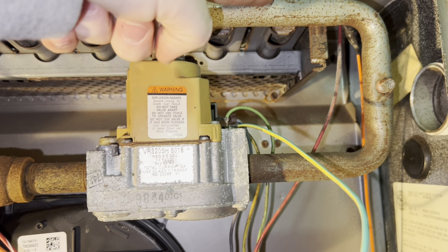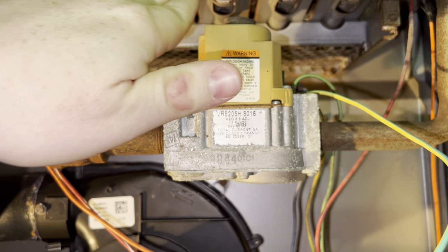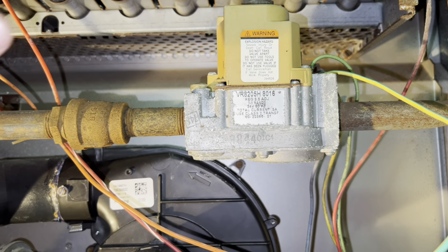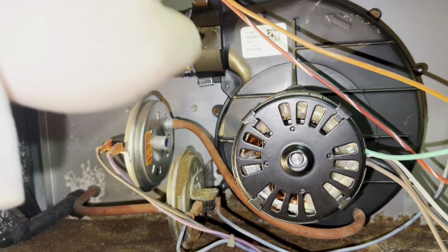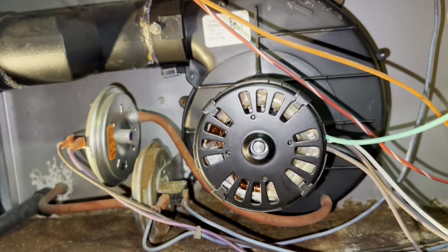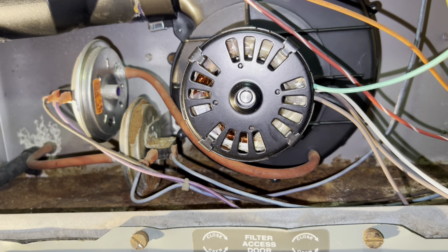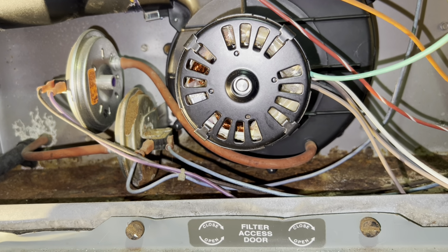And once we are confirmed we don't have any safeties out, the HSI or spark, in this situation it's going to be a spark igniter that's located right up here, is going to start sparking. Our gas valve is going to open. The burners are going to light all the way across. And once they light all the way across, the flame is then going to be proven right here, all the way down. Now we're going to heat up, and then we're going to turn the blower on delay. We want that blower on delay so everything is nice and hot whenever the air moves across, it's delivered to the house.